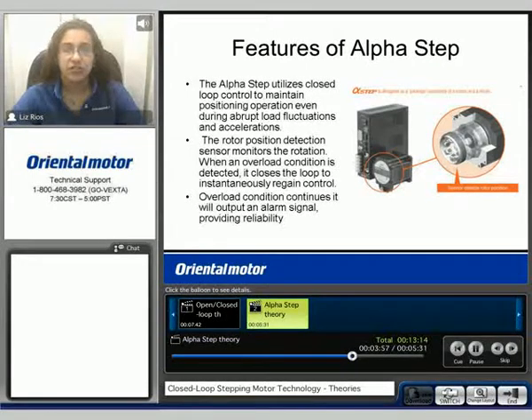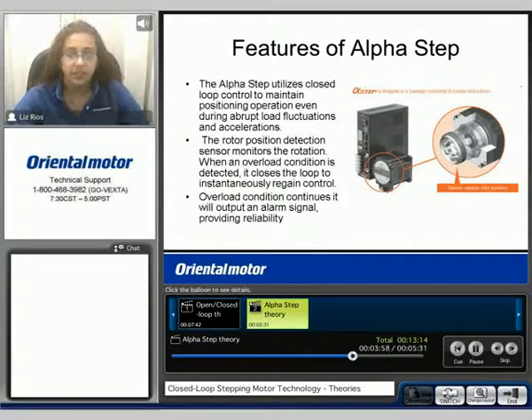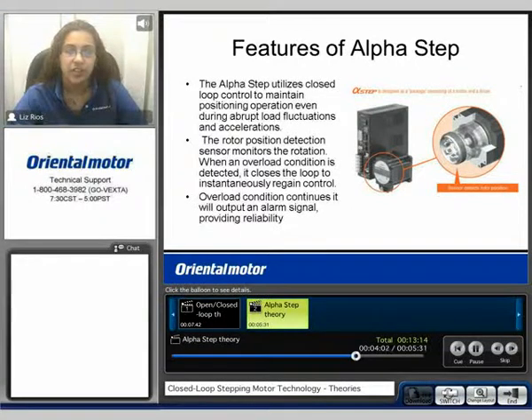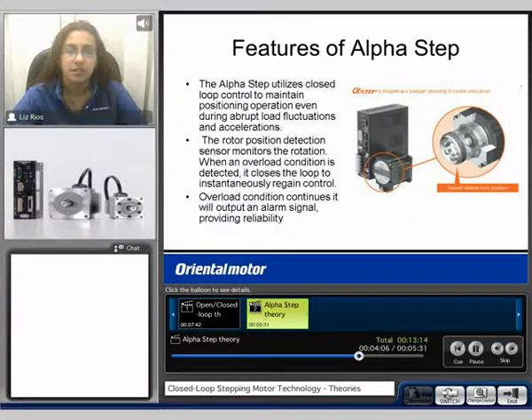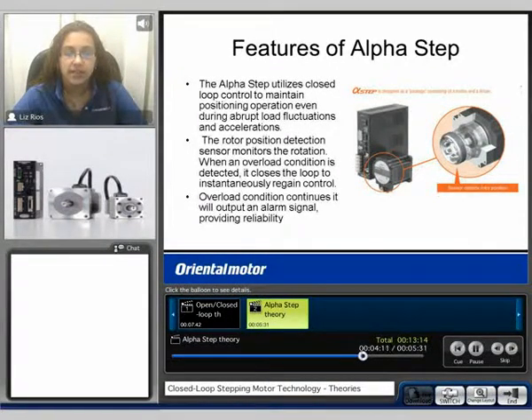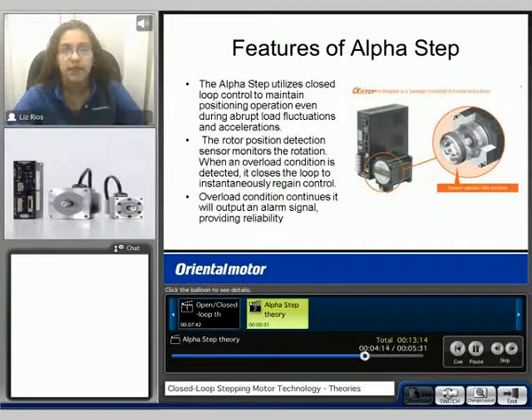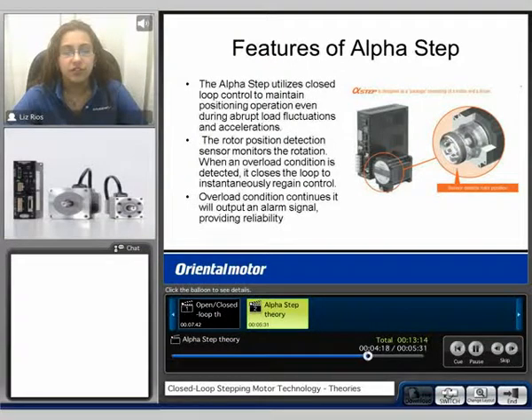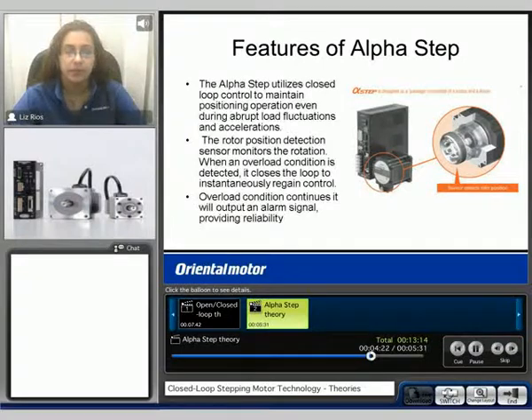Here are some highlighted features of the AlphaStep. It utilizes a closed loop control to maintain positioning operation even during abrupt load fluctuations and accelerations. The resolver monitors the rotation. When an overload condition is detected, it closes the loop to instantaneously regain control. And if the overload condition continues, it will output an alarm signal providing reliability.